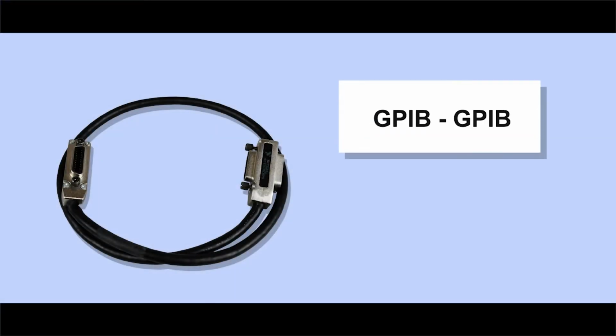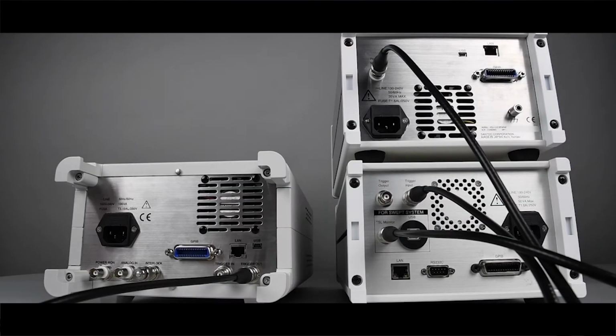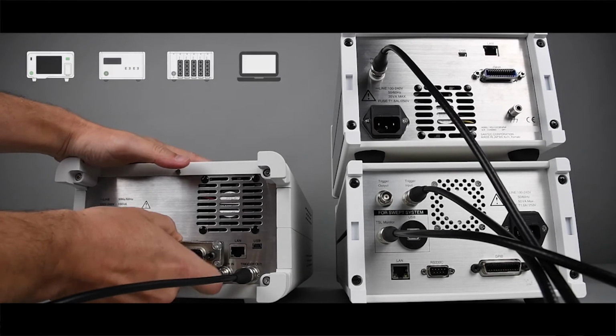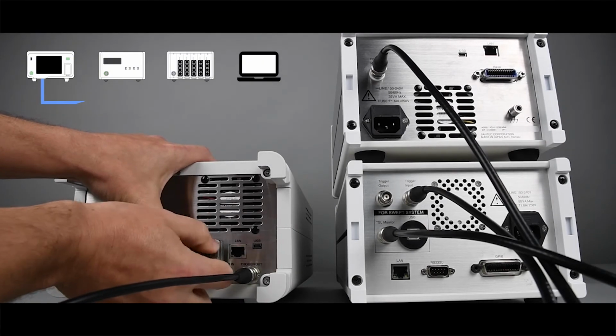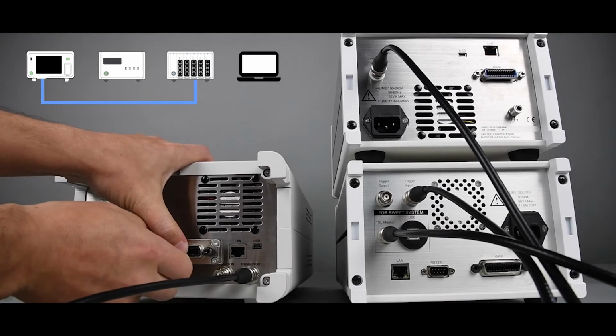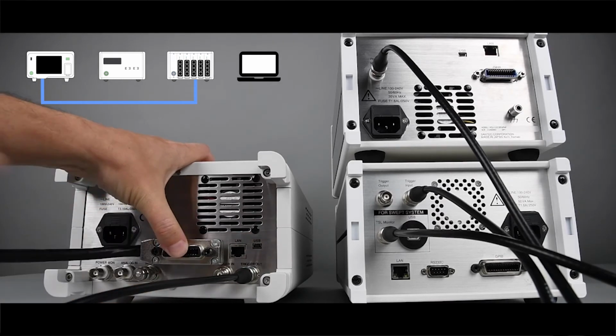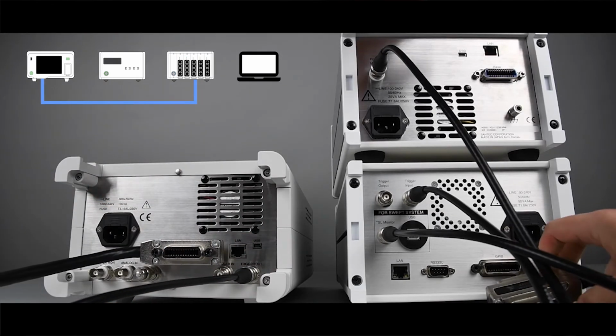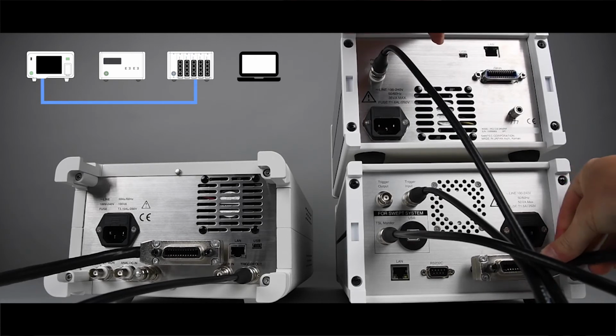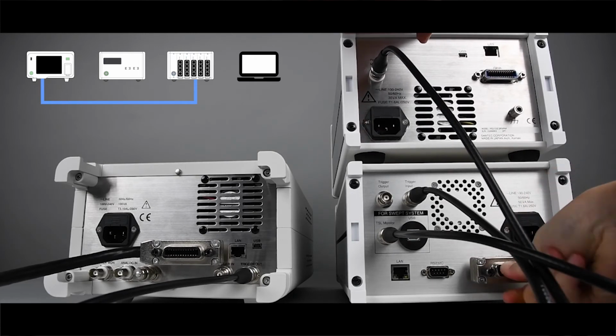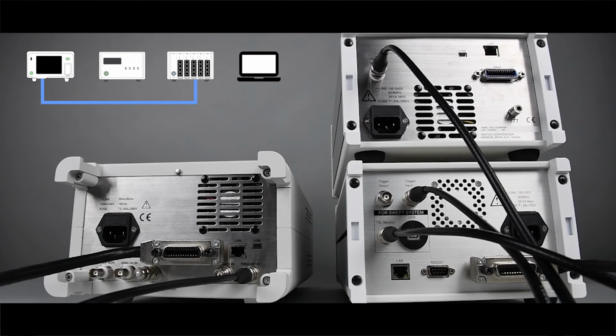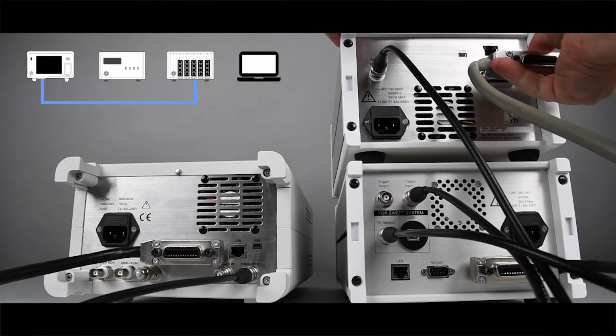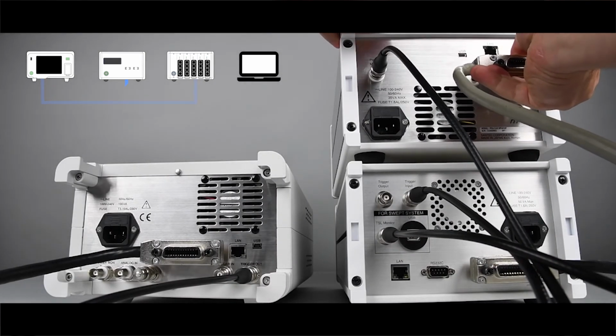The GPIB cable allows all instruments to use the same GPIB port while maintaining their own respective addresses. For that, just connect the first GPIB cable between the TSL and the MPM, and the second GPIB cable between the PCU and the MPM.